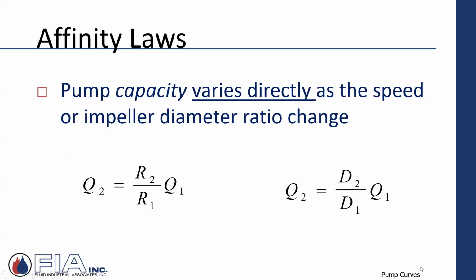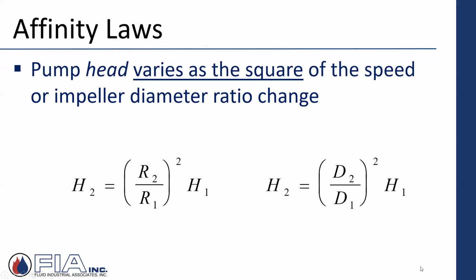So the three laws, if you will, the three pieces of information to take away. The pump capacity varies directly. It's a one-to-one relationship as the speed changes. So if I have a certain speed, I cut it in half, my flow rate is exactly in half. That's pump affinity law 1. Number 2 talks about the pump head. That's the part that varies as the square. So when I change the speed, in this case RPM, it's a squared relationship. So that head drops by a square, or it increases by a square, as I increase or decrease that speed.